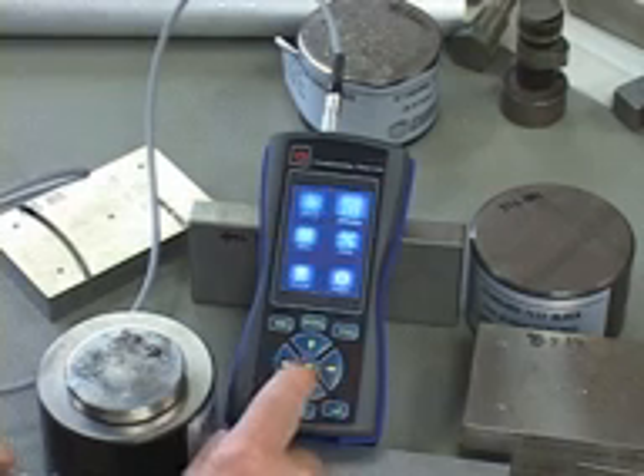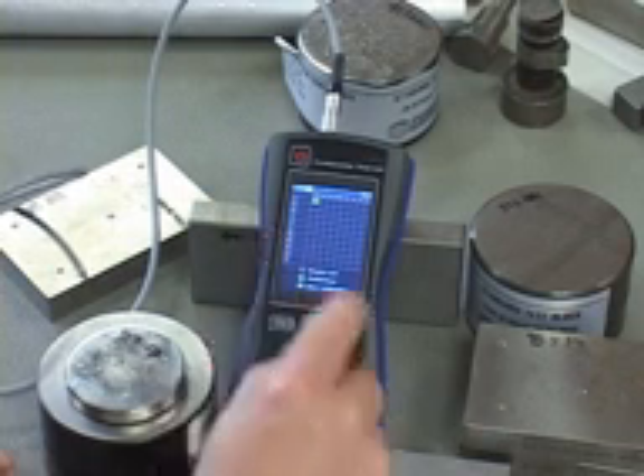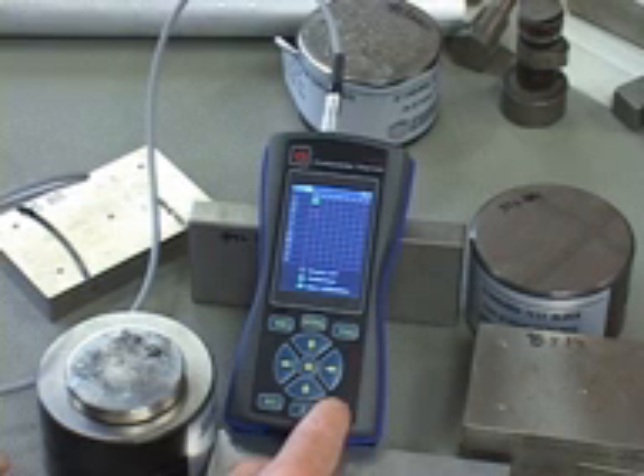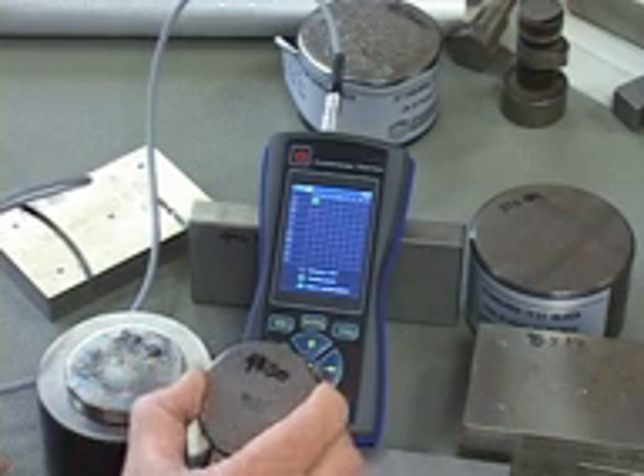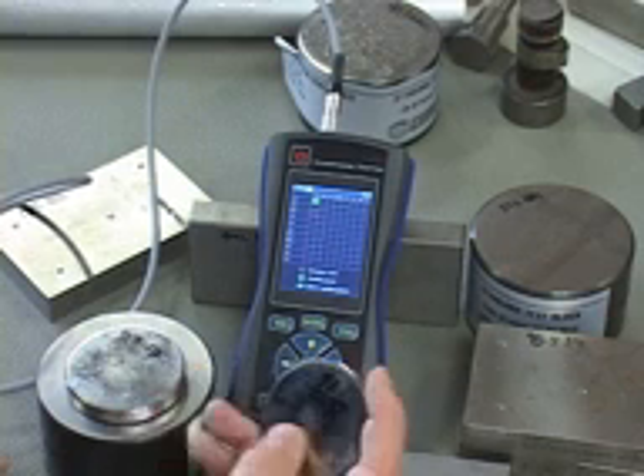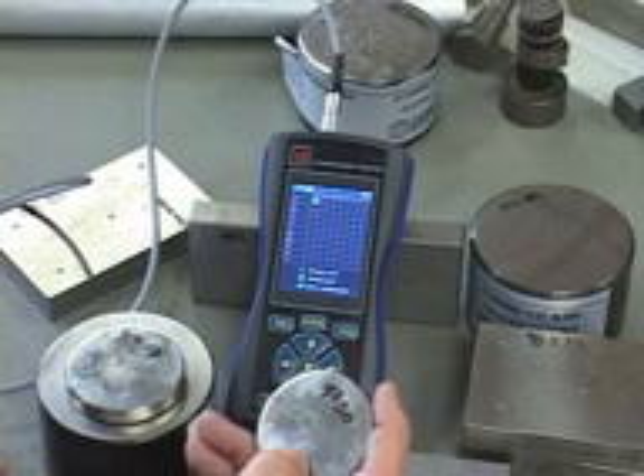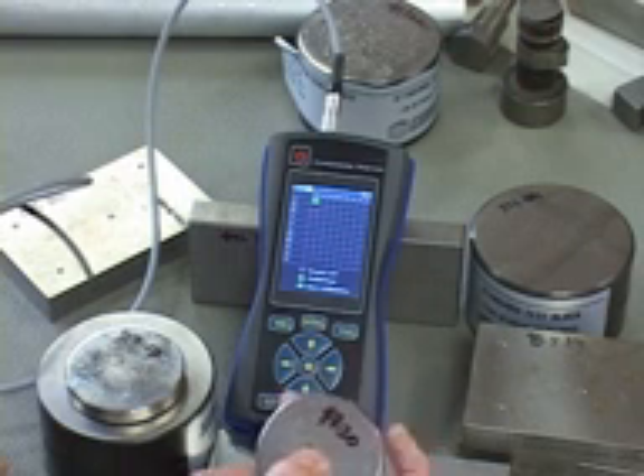Very, very simple. If you wanted to do calibration for additional materials, you would then go back into the calibration mode, move your cursor around, for example stainless steel, SST. You would hit the return key and go through the same steps that I did. You probably wouldn't have calibration blocks, but you'd have your own materials in stainless steel of 3 different known hardnesses. They don't have to be polished like this. They've got to be a good surface finish, of course. But then you can calibrate the unit for your own materials, titanium, very exotic stainless steels, very exotic sorts of materials that are difficult to test otherwise, are great for an ultrasonic tester.